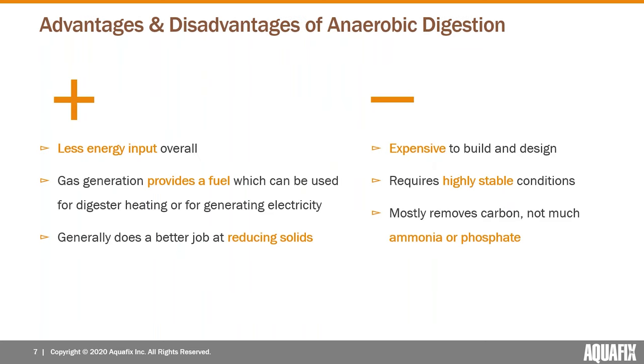Anaerobic digestion has some advantages and disadvantages compared to aerobic digestion. The main disadvantage is they're expensive to build and design — that's why you usually won't see anaerobic digesters in very small municipal plants. Smaller systems also have less stable waste streams, which anaerobic digesters require, making upsets more likely. Additionally, they're mainly removing carbon and aren't efficient at removing ammonia and phosphate, so they're typically coupled with aerobic treatment.